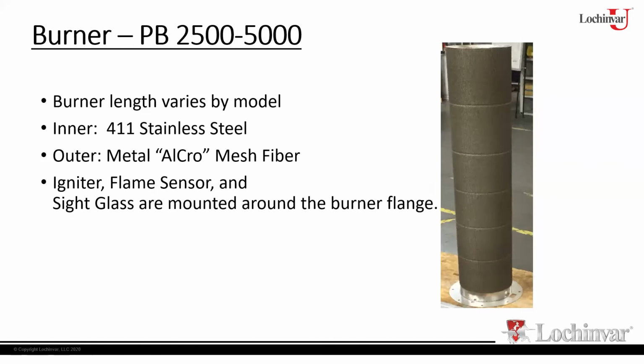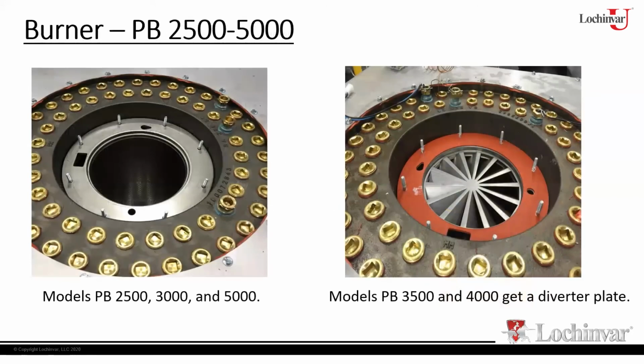Now with the bigger models also, you will see on two of the models, the 3.5 and the 4 million, they're also going to get this diverter plate that you see here. Diverter plate, stabilizer, whatever you wish to call it, basically that is needed on those particular models based on the length of the burner itself, the size of the combustion chamber. During our testing, you would get a little noise from it. So to remove the noise from the combustion process, we put this device in here, which I guess smooths out or balances the gas air mixture as it goes into the burner.